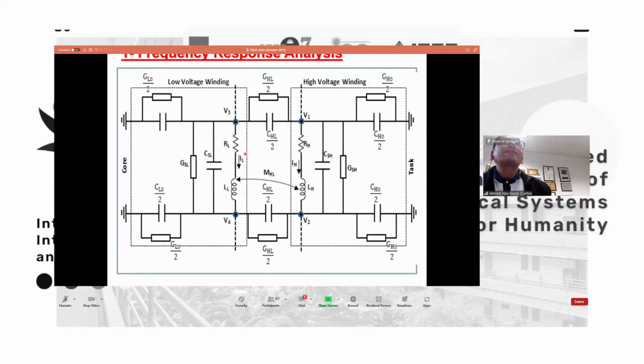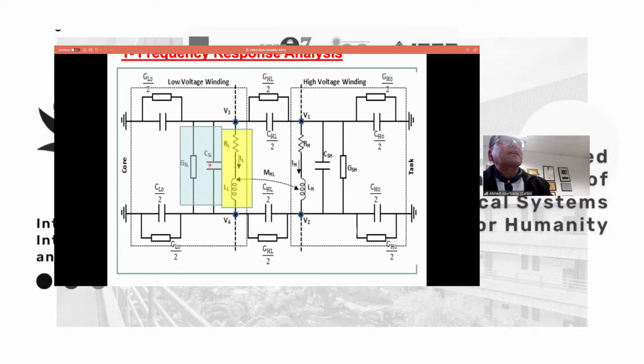That's one disk or one turn only. So I put some animation here just to follow me. We start with the low voltage winding, which can be represented by series inductive elements, R and L. And because this winding has insulation paper between the turns, the insulation paper can be simulated as a dielectric capacitor shunted by dielectric conductance. Similarly, we have the high voltage winding, which can be represented by inductive elements shunted by dielectric capacitance and conductance.